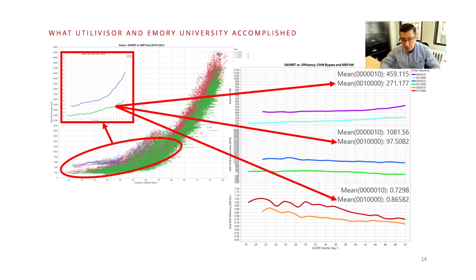Once we got confidence from the team, they implemented all those ECMs, and then we expanded out to some of the cross connect plants. Again, same kind of theory, where we looked first at the chiller controls. In one plant in particular, they had a higher head pressure control, where, at those part load conditions, we wanted to make sure you got the biggest bang for energy savings. So we modified some of the control loop so that the head pressure control didn't open as soon, and the lift was reduced, so the chiller saved energy at those lower conditions.